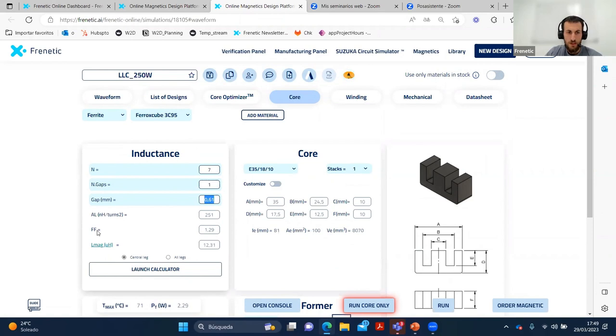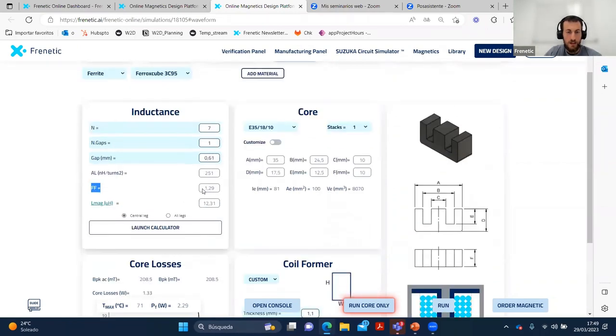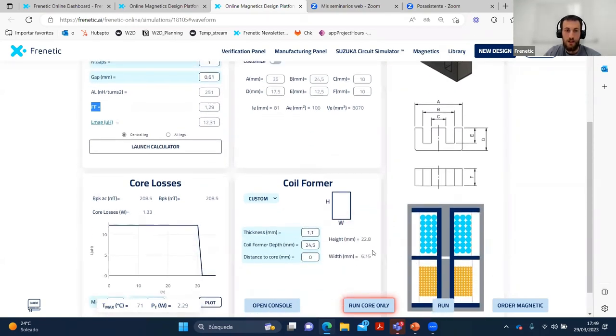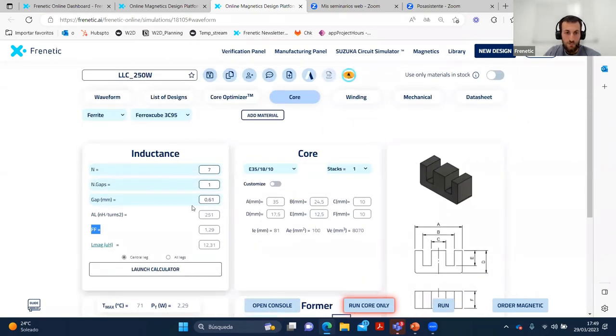You need to know what the fringing field factor is, and there are some equations for this that we can solve in a separate webinar. And based on this fringing field factor, you know if the gap is too big or not. So the bigger this number, the bigger the gap is. The bigger the gap, the more losses you will have in the windings.